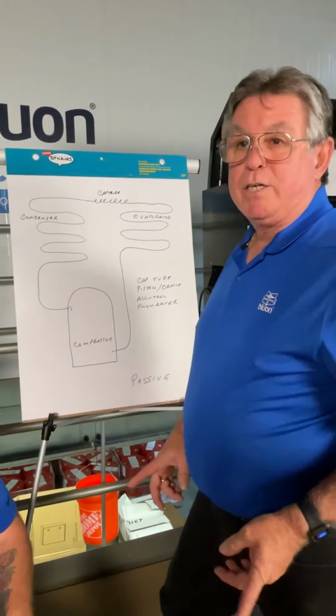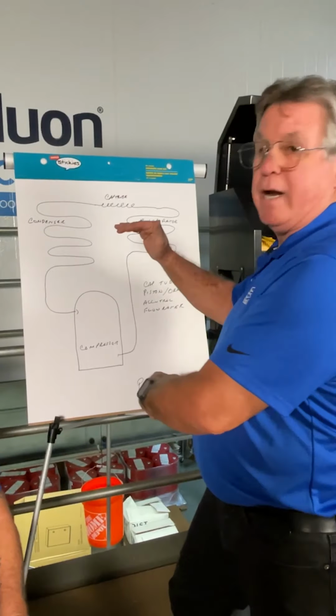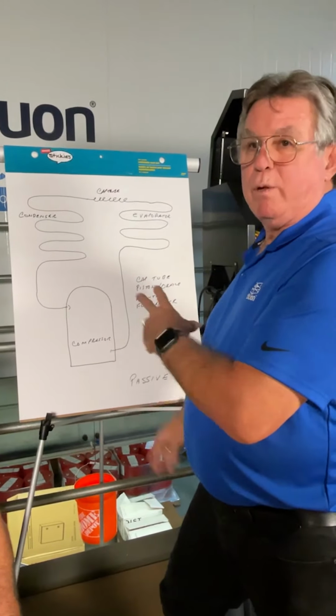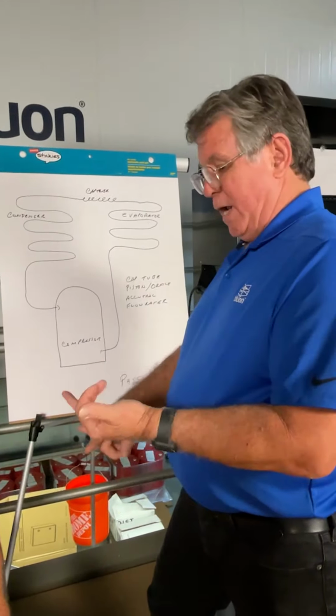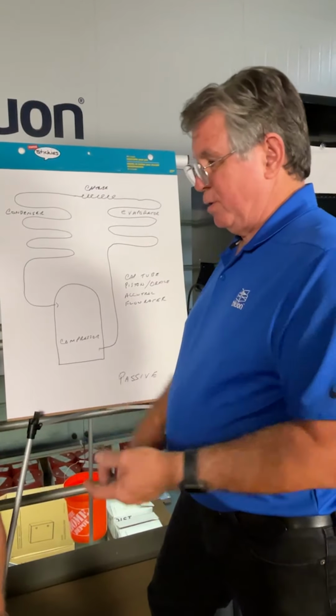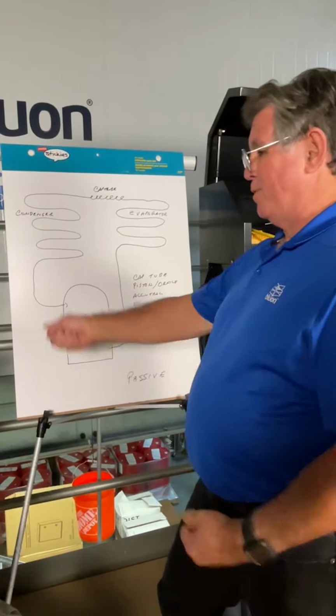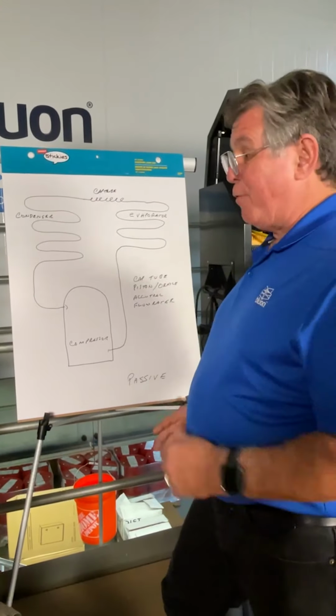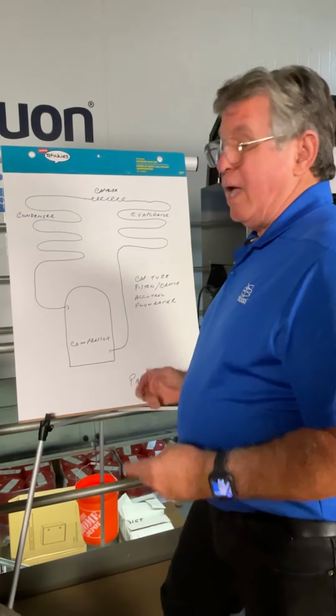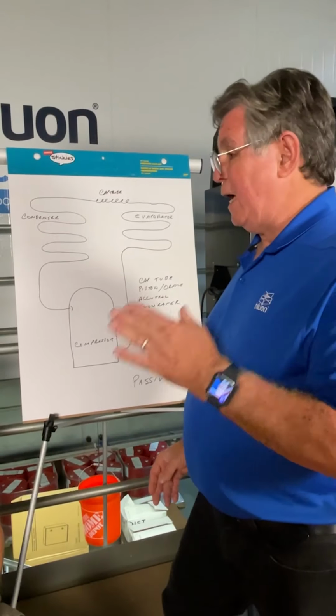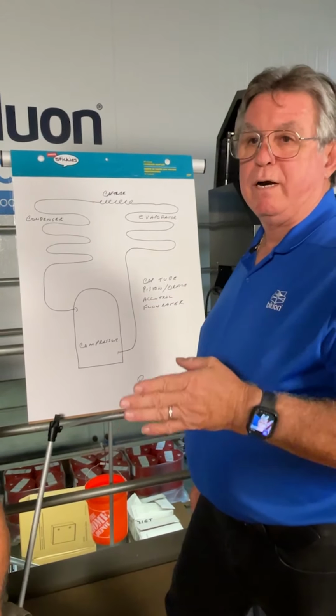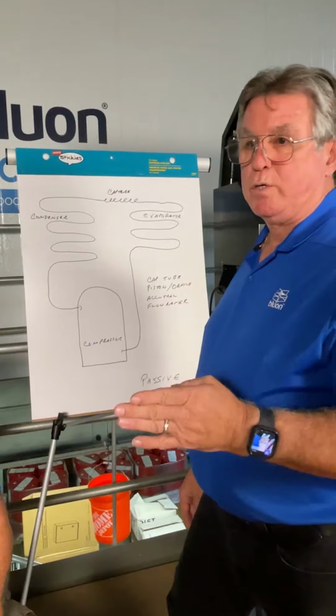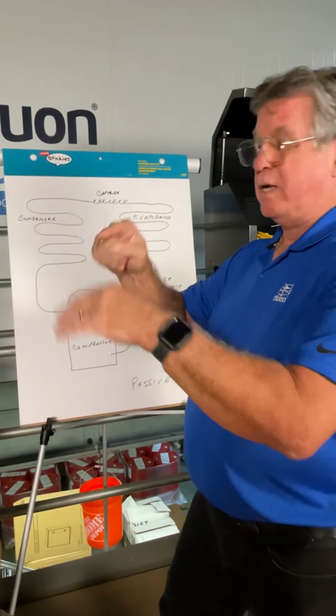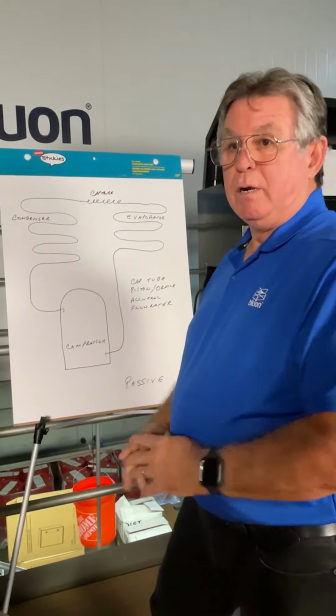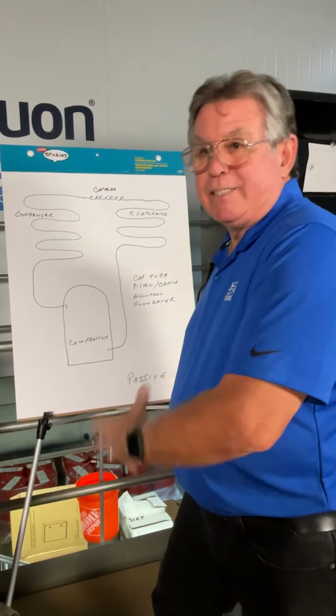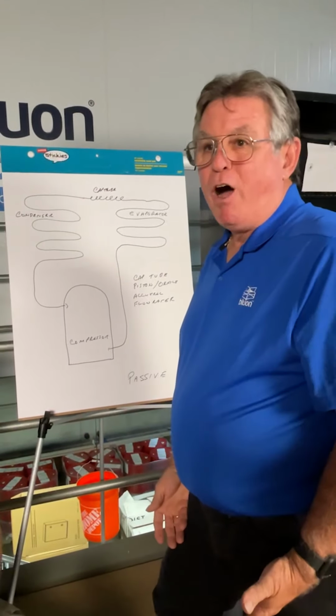Now, most manufacturers were really, really nice. They put this really nice sticker on the side of the unit. Well, that was great. There was only one little problem. There's this thing called rain and sun and smog and air pollution and everything else, and the guy throwing the panel across the ground. So you get out there and there's nothing there. And basically all you're doing is you're taking a return air wet bulb and an outdoor dry bulb, and you're bringing the two things across, and it gives you a target superheat. Well, that's great if you've got all the data still there. The problem is most of the time it's gone.